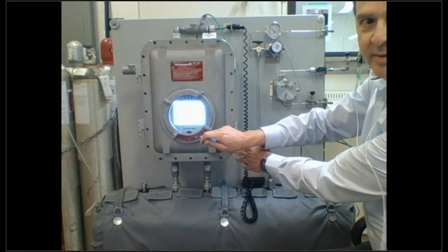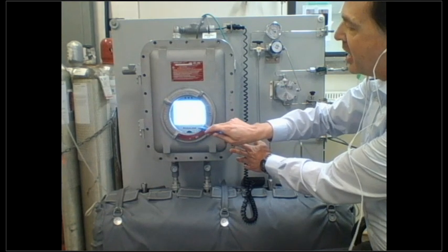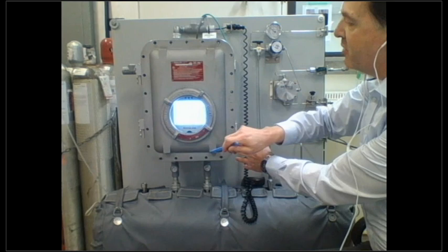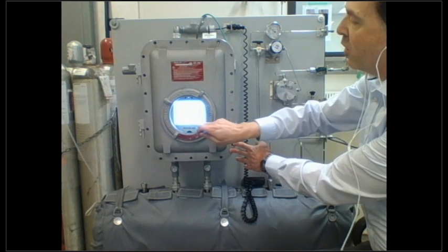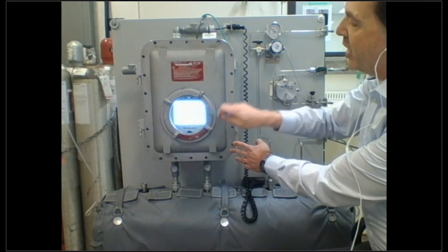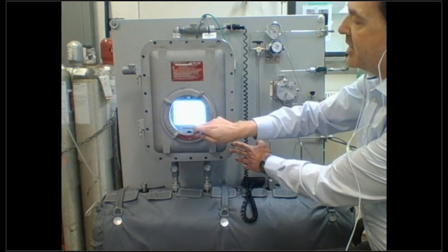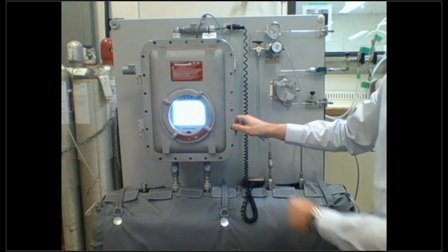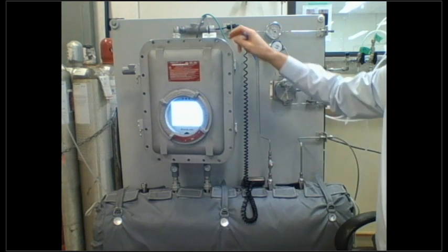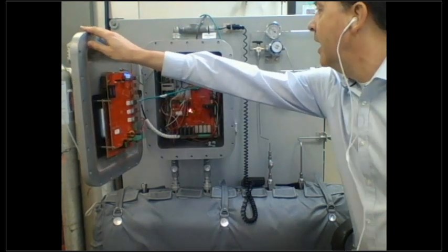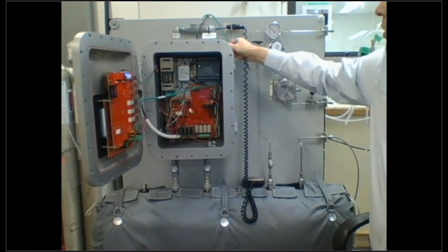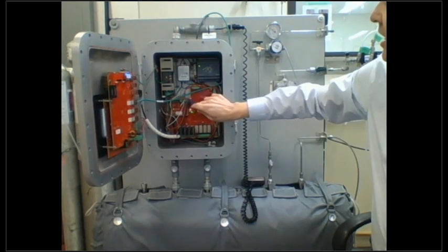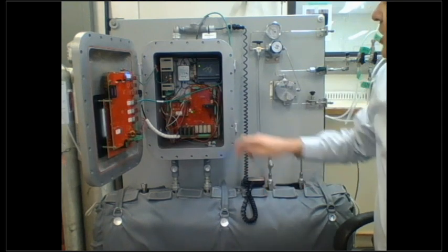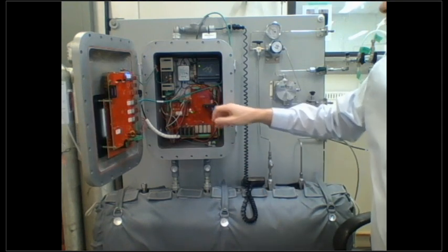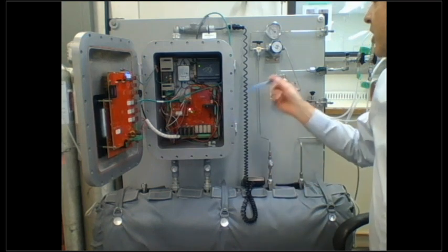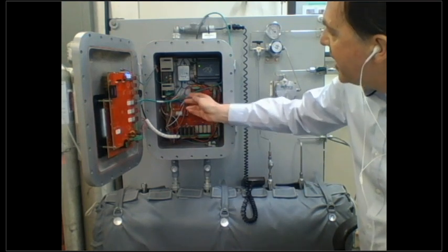That port is accessed through the front panel. It may be difficult to see. This display is a little bit too bright for the webcam, but if you open the explosion-proof window, you can actually access that Ethernet hub without having to open the enclosure. Also located inside, this is the main board in the back here. This is where all of the inputs and outputs are handled. For example, along the side here, we have all the inputs associated with measuring the pressure and temperature of the laser. Along the bottom are the customer outputs.